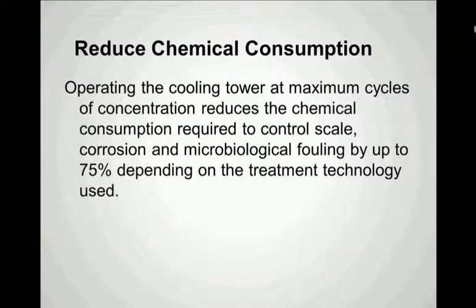One of the requirements for most cooling towers is chemical treatment for scale, corrosion, and microbiological fouling. Operating the cooling tower at maximum cycles reduces the chemical consumption required to control scale, corrosion, and microbiological fouling by up to 75 percent, depending on the treatment technology used — a very favorable effect on the amounts of chemical required to properly treat the cooling tower.